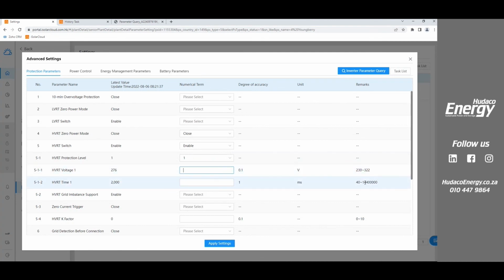And I mean, you can set it for a huge amount of time. Be aware, if I set this for 276 for 1.44 million seconds, I'm going to break the unit, right? And then when you come to a warranty claim, we'll see what's happening, and they're going to say, hang on, why did you do that? So try and keep it within your limits. 253 should be your limit.